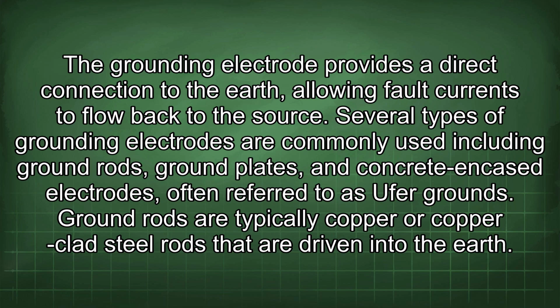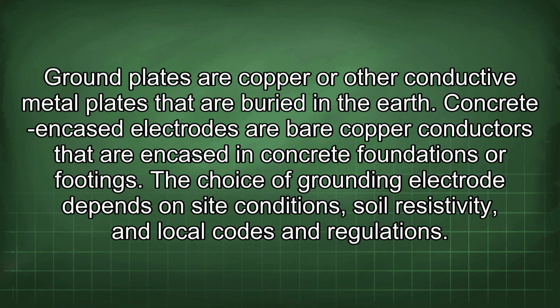Several types of grounding electrodes are commonly used, including ground rods, ground plates, and concrete-encased electrodes, often referred to as Ufer grounds. Ground rods are typically copper or copper-clad steel rods that are driven into the earth. Ground plates are copper or other conductive metal plates that are buried in the earth. Concrete-encased electrodes are bare copper conductors that are encased in concrete foundations or footings. The choice of grounding electrode depends on site conditions, soil resistivity, and local codes and regulations.